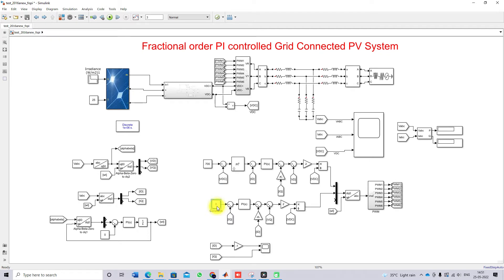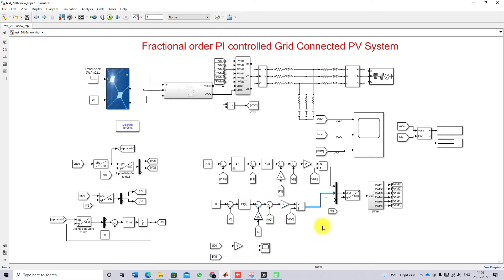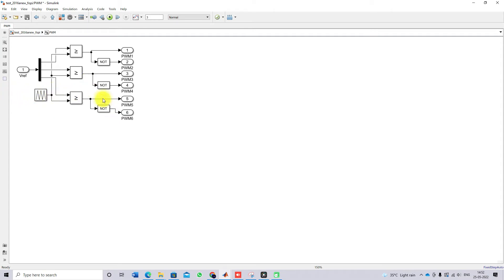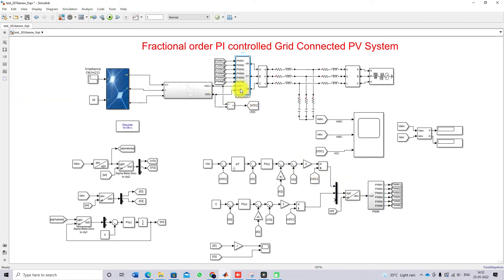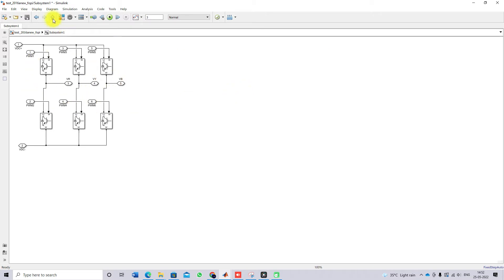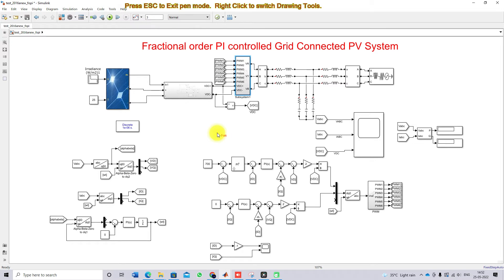The iq reference is set to zero because we are sending only real power, not reactive power. The iq reference is compared with the actual iq of the inverter, processed via the PI controller with feed-forward compensation, and generates the control voltage in the q-axis. The dq0 signals are converted back using inverse Park transformation, generating pulses for the three-phase inverter to control the real power flow from the PV to the grid.